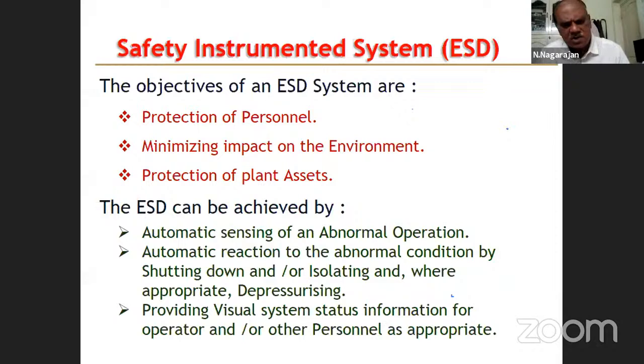And then you have visual system, means alarms will come, you will see blinking lights, and then hooter sounds, alarm sounds. There are different sound levels depending upon the type of the hazard, and that is part of the safety system design. So this is to alert the personnel and take appropriate action.